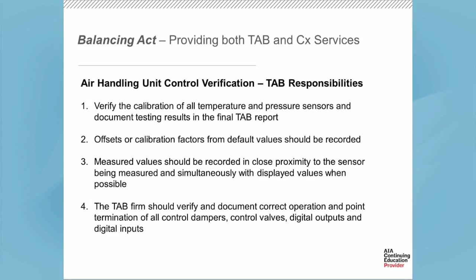So when we get into the HVAC functional testing role, I'm going to change gears here, and now we're into the functional testing stage of the project. And the commissioning provider is going to be leading this to conduct the functional testing activities. So what then does the TAB team do to support that process? They're going to be there to measure flows, pressures, electrical data, and temperatures required to verify performance. Oftentimes, this is not needed if you have a robust BAS system and all this has been done in advance. But we do find instances where this needs to be verified during the functional testing.